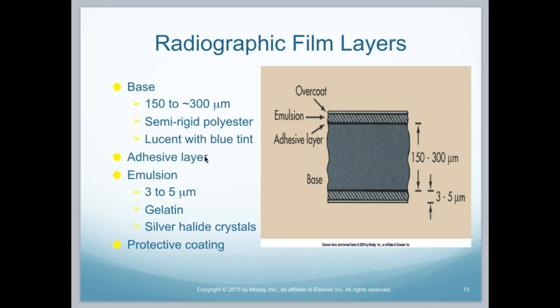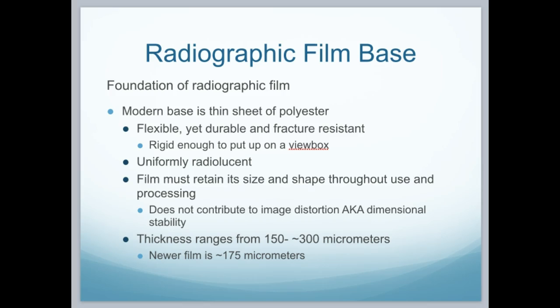We also have an adhesive layer with an emulsion. The emulsion is 3 to 5 micrometers. It's composed of gelatin which has the silver halide crystals in it, and then we have a protective coating over the top. The foundation of the radiographic film base is a thin sheet of polyester — very durable and resistant to fractures, rigid enough to be put up on a view box hundreds of times. The radiolucency is very uniform. The film retains its size and shape throughout processing, and does not contribute to image distortion or dimensional instability. Typical film ranges from 150 to 300 micrometers, but newer film is about 175 micrometers.